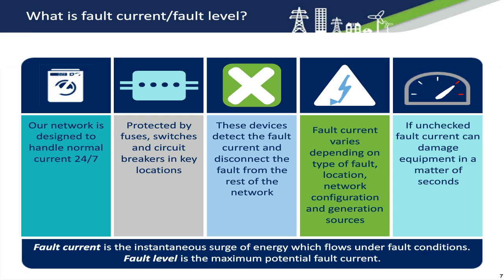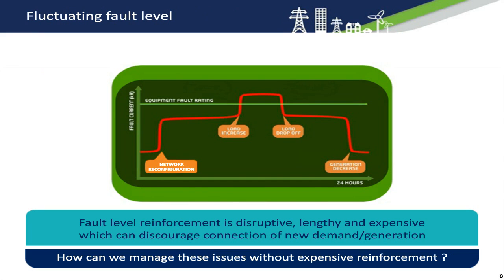We know the maximum potential fault current changes during the day, as seen on the graph, as we change and configure the network and sources of generation are switched on and off. Using our historic design models, we predict what the worst case fault level will be to ensure the network operates safely, taking into account the maximum rate at which the equipment can safely perform.